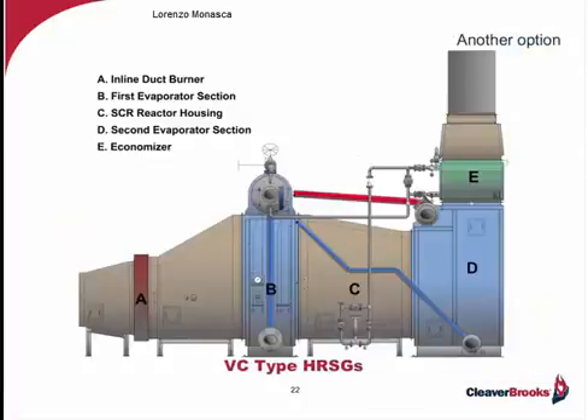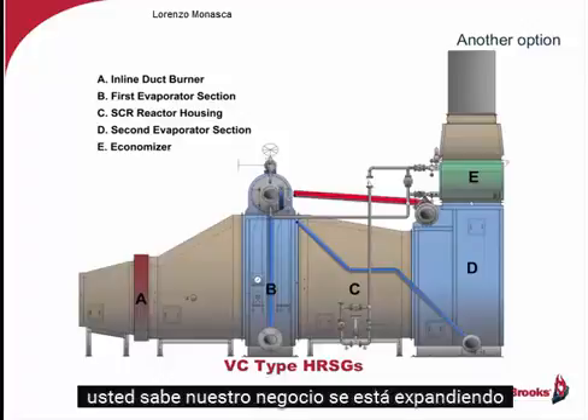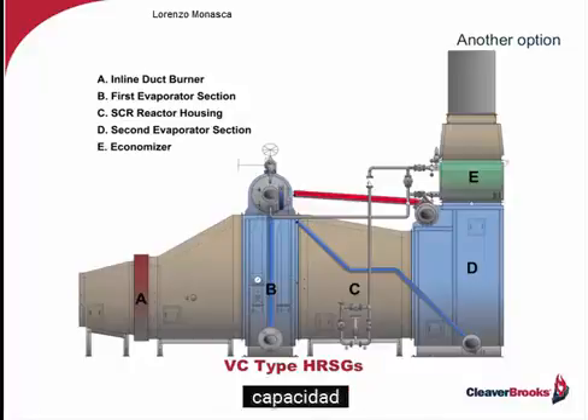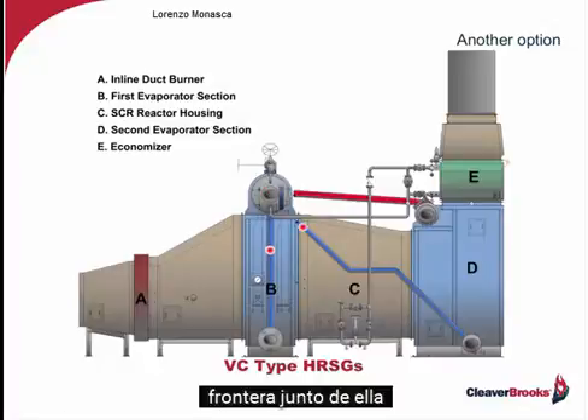Now, this customer in this particular case was also saying, you know, our business is expanding. And what we've designed so far is fine for the immediate needs. But later on, we might be requiring some additional capacity. Well, we started off with this cross-flow diagonal boiler. Later on, we could easily handle additional capacity by putting in a drum-over-drum boiler alongside of it, cross-connecting our downcomers and our steam outlets. So everything is now coming out of this main evaporator, if you will, this drum-over-drum boiler.